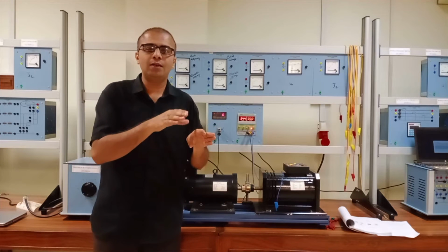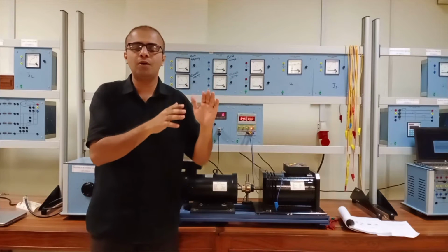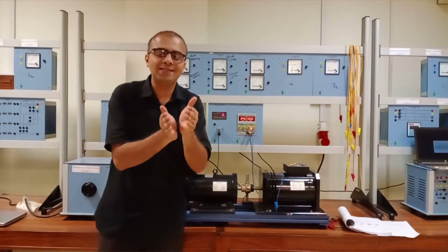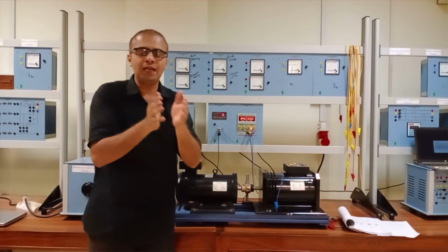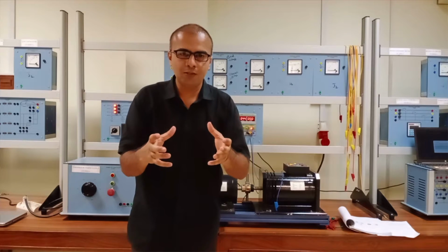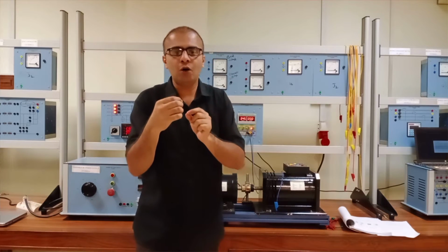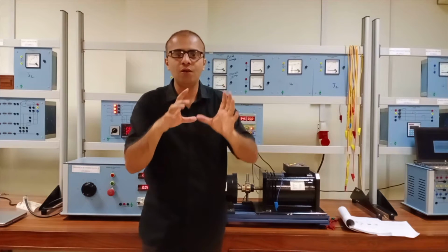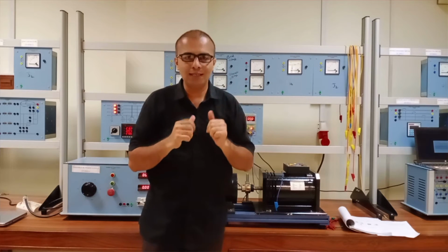Obviously you already know that the terminal voltage E0 of the alternator totally depends upon the field excitation which is to be given to the field winding of the alternator. If the DC field excitation of the alternator is increased, then our output voltage E0 will be increased. So for this purpose, today we have to conduct the open circuit test of the alternator to vary the amount of the DC field excitation to the field winding. We have to analyze what the effect on the stator voltage will be by changing the field excitation.